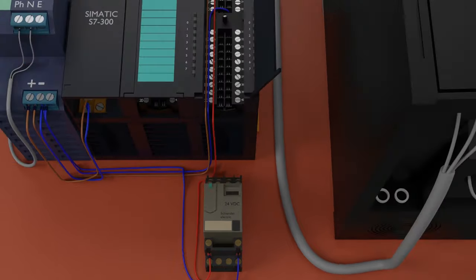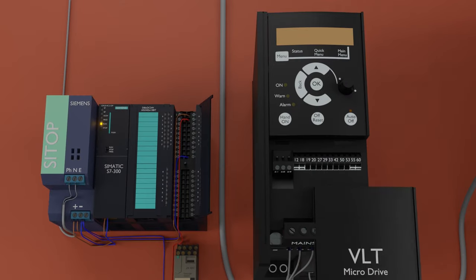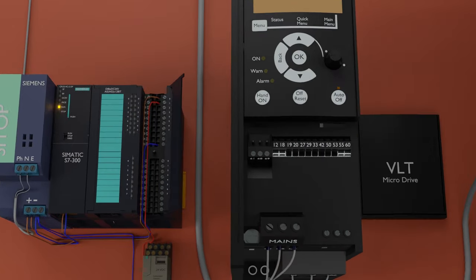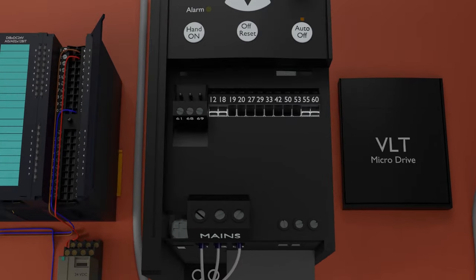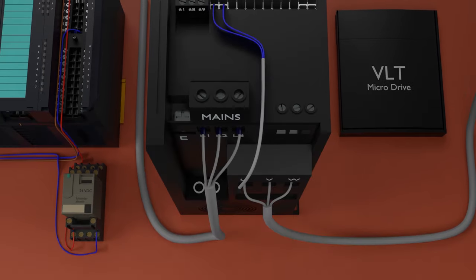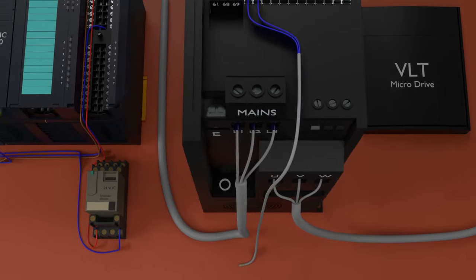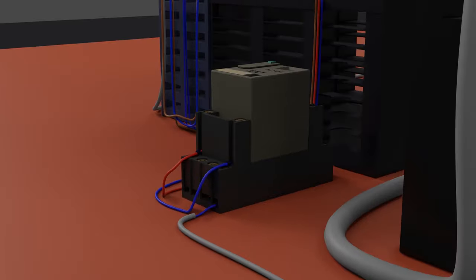This relay will be used to give a run command signal to the VFD. To do this, we will connect two control wires at terminals 12 and 18. One control wire we will connect at the common terminal of the relay, and the other control wire we will connect at the normally open contact of the relay. When this relay turns on, these two wires short and the VFD gets a run command signal.